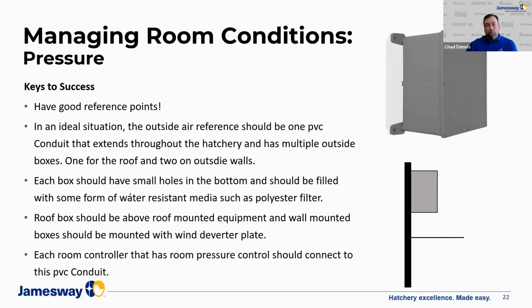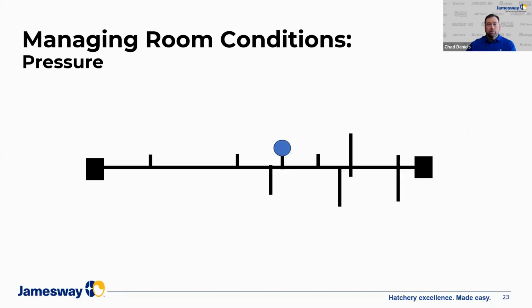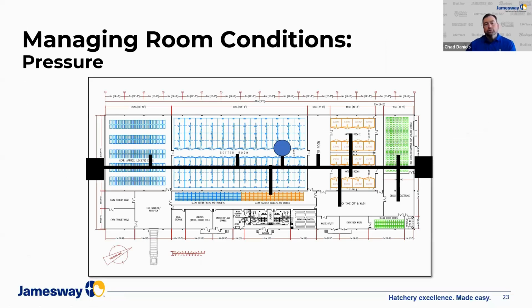So each room controller that has room pressure control should connect to this primary PVC conduit. In this illustration, when we look at a typical layout for a hatchery, we see one conduit that runs through the facility with an outside reference on one end or on each end, and then in the middle, it has an outside reference up through the roof. And so each room, whether it's a washroom or a takeoff room or transfer room or hatchery rooms, chick rooms, incubator rooms, every one of those rooms has a connection to that one conduit. So when you look at a room and say this is a 0.02 positive to atmosphere, and this room is a 0.015 positive to atmosphere, they both have the same reference to atmosphere.